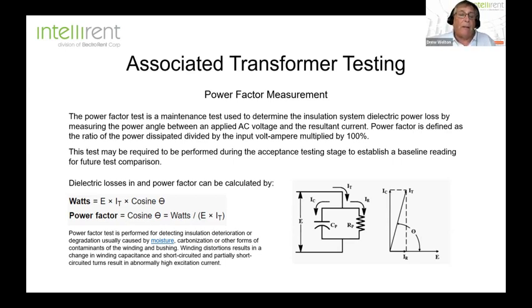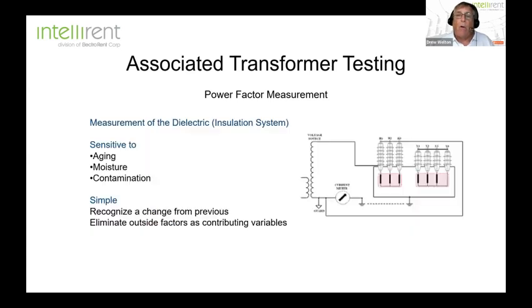So the very first thing that people have relied on is, of course, doing your power factor measurement. If you see an increase in your power factor, that means you have some type of deterioration in the insulating system. That can be moisture, carbonization, or other forms of contaminants in the windings, and of course in your bushings. So this is a fundamental test. We've been doing it for years, and basically what it's telling you is the overall health of the insulating system itself.